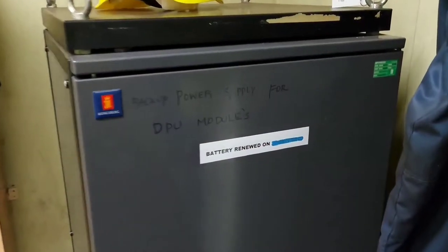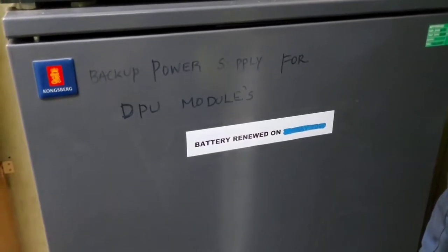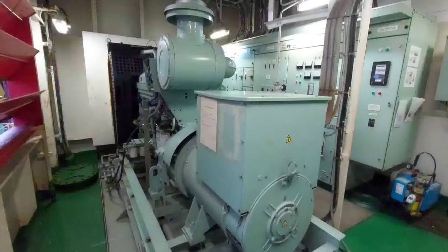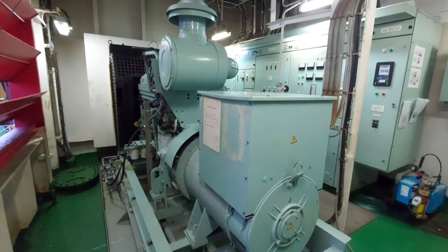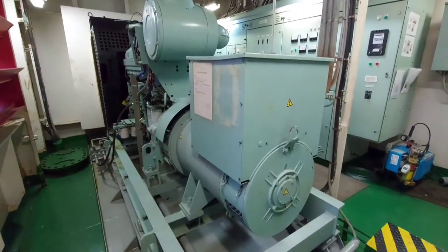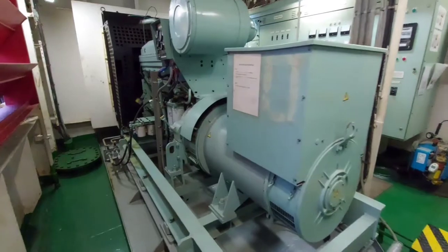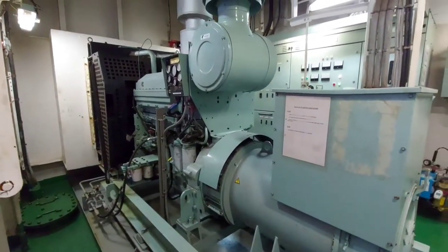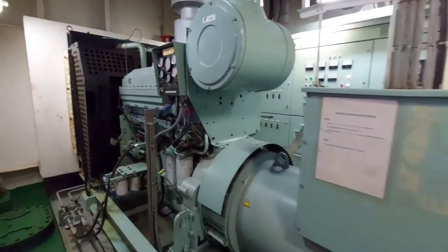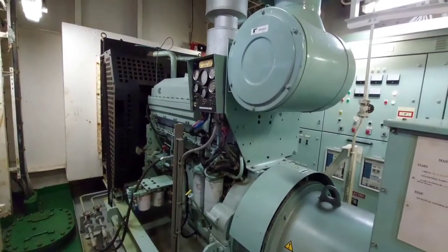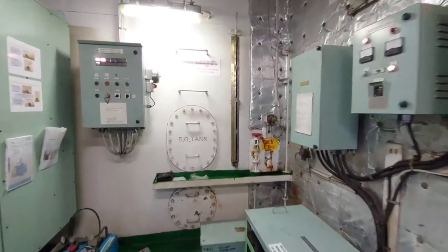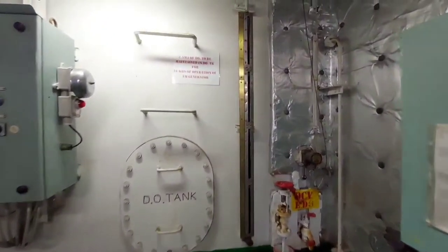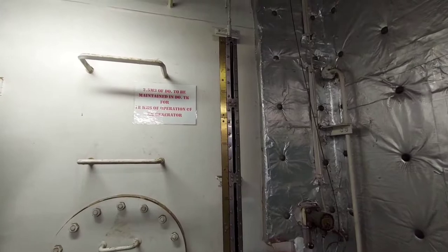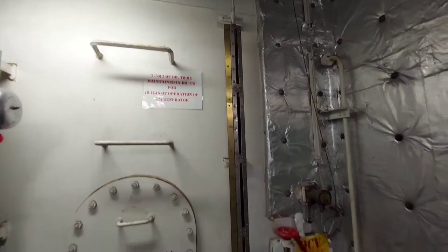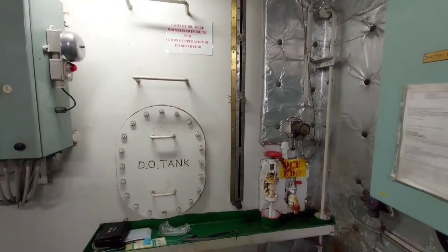Apart from this we have a battery unit to produce electricity, and also we have an emergency generator, which is a requirement. If there is no source of power, or if the main generators are out and we cannot start the main generator, at that time we will be using this emergency generator. This is having a separate diesel oil tank also. This emergency generator is normally located outside the engine room, normally in the upper continuous deck.